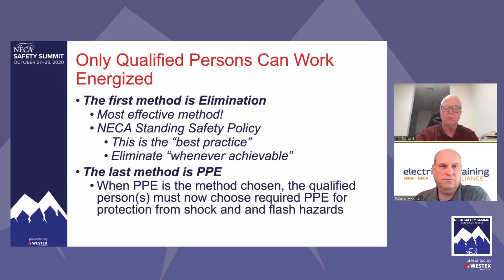Palmer, on the PPE? Yeah, so when we do get to the sixth of the six hierarchy risk control methods, there's two different things to consider. Personal protective equipment, and we have some examples here: rubber insulating gloves, leather protectors, arc-rated garments, arc-rated face shields, and then we have other protective equipment. So PPE, we all know, is in 130.7(C), and then other protective equipment is in 130.7(D), such as insulated tools, which have to be provided by the employer based on the hazard assessment. And test equipment.